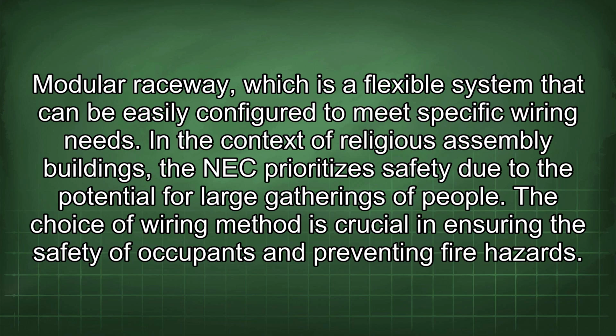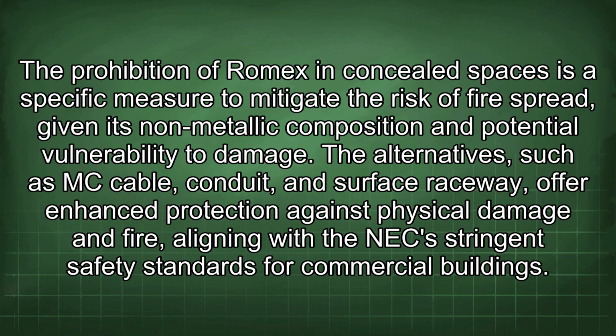In the context of religious or assembly buildings, the NEC prioritizes safety due to the potential for large gatherings of people. The choice of wiring method is crucial in ensuring the safety of occupants and preventing fire hazards. The prohibition of Romex in concealed spaces is a specific measure to mitigate the risk of fire spread, given its non-metallic composition and potential vulnerability to damage. The alternatives, such as MC cable, conduit, and surface raceway, offer enhanced protection against physical damage and fire, aligning with NEC's stringent safety standards for commercial buildings.